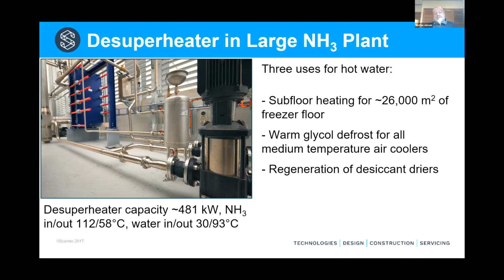And the third use is regeneration of desiccant dryers. Desiccant dryers are used in large freezer applications to prevent slippery floors. Slippery floors are dangerous. When people fall over, they lodge a workers' compensation claim, and that's what we're trying to avoid. So the regeneration of a desiccant dryer happens by pumping warm air of 60 to 70 degrees through a corner of the desiccant wheel to drive the moisture out. The warm air is heated with the hot water that comes from the desuperheater.